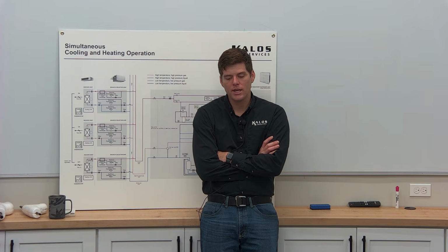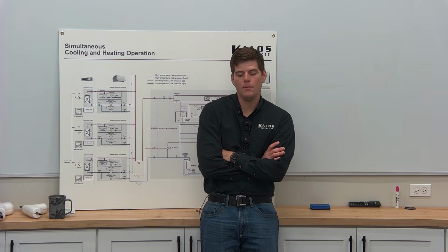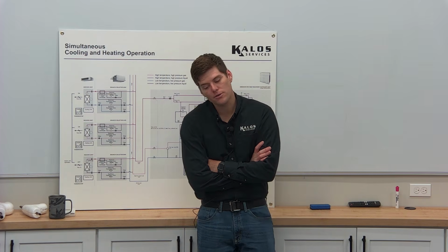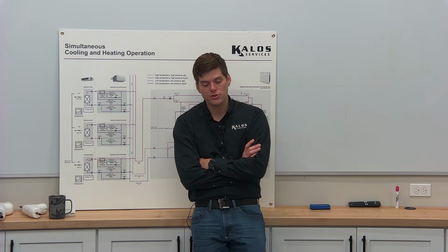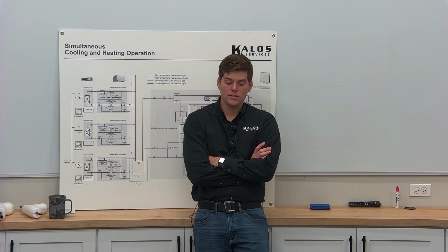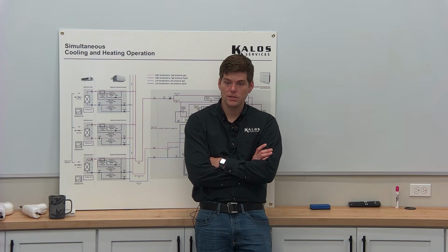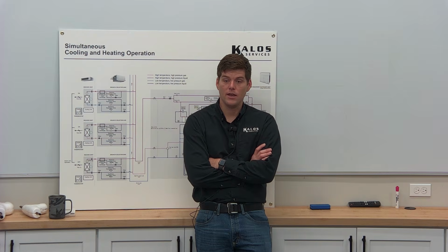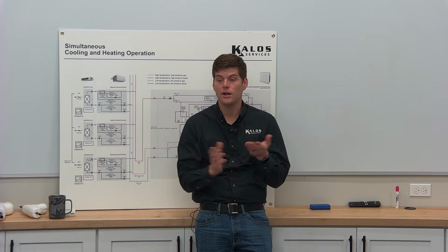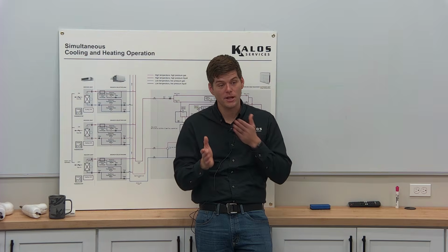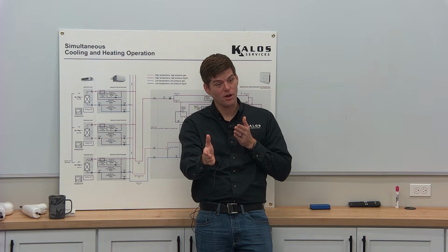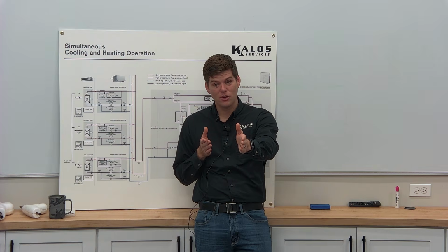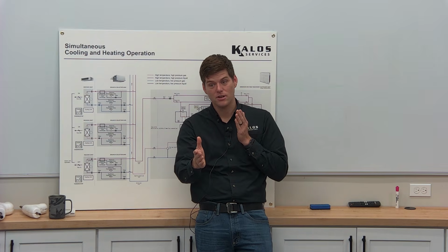Yeah, so we're gonna get to that, but it's a good question. So every manufacturer is different, right? So Samsung's short relationship with Trane resulted in solenoid valves in the branch selector boxes. They only change. It's like a 4-way valve, guys. It's determining which way traffic's going. Are we going this way? Is hot gas going this way, or am I going to just do suction and liquid, right?